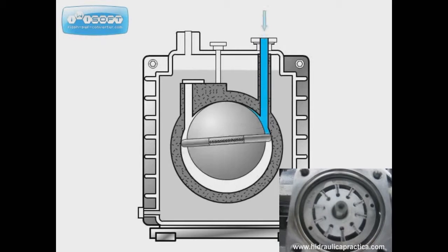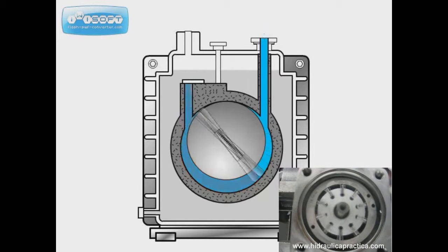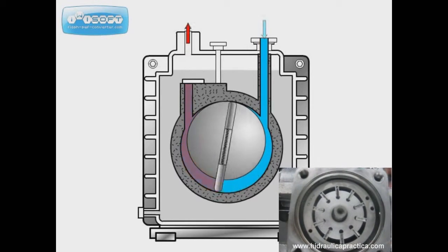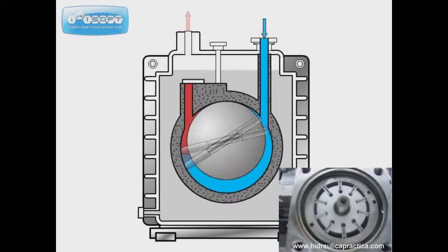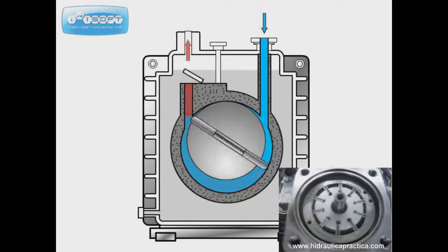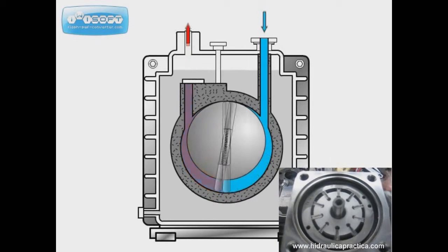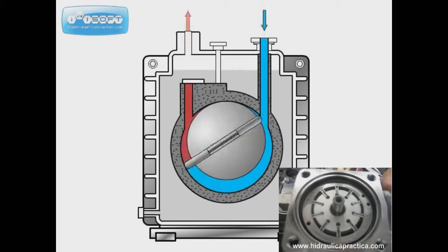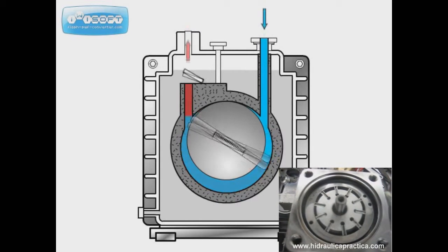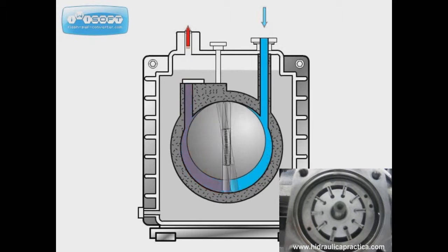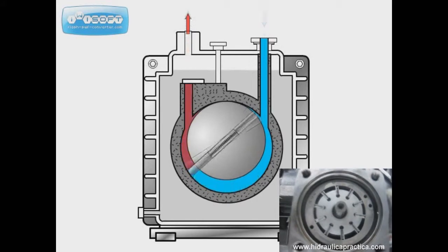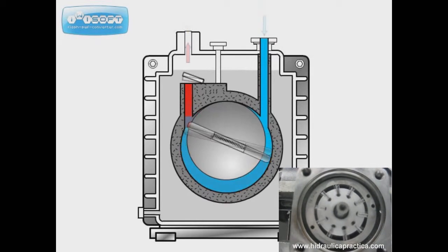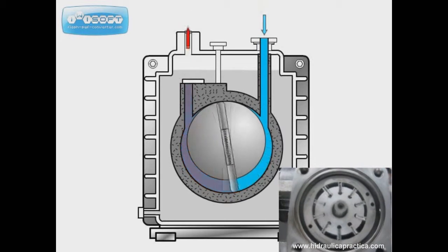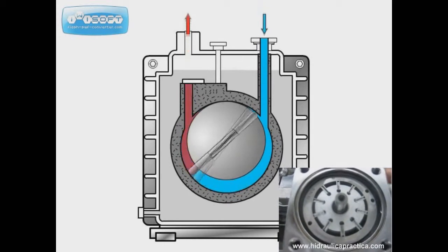The simplest vane pump is a circular rotor rotating inside of a larger circular cavity. The centers of these two circles are offset, causing eccentricity. Vanes are allowed to slide into and out of the rotor and seal on all edges, creating vane chambers that do the pumping work. On the intake side of the pump, the vane chambers are increasing in volume.